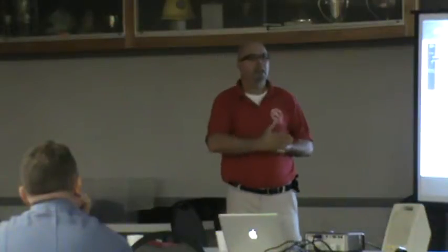Any building that's 50 to 75 years old, we recommend that the fire escape be load tested, but you give them a 5-year heads up: hey, we'll take this confidence test now, good job on refurbishing it, but be aware that between now and 5 years, we would like a load test, and then every 25 years on that building. So that's our recommendation, that a fire escape goes minimally once in its lifetime through a load test, and depending how old it is, you can initiate that.